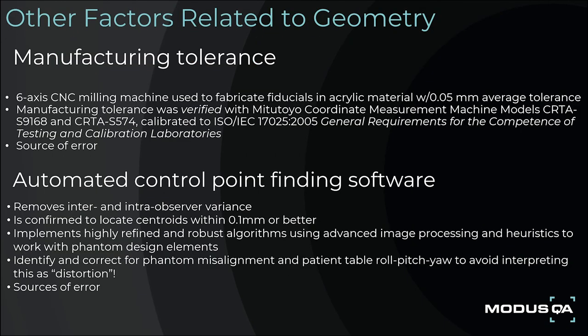Other sources of error related to geometry include manufacturing tolerances. Modus QA uses a six-axis CNC milling machine to fabricate fiducials in acrylic material with 0.05 mm average tolerance. This manufacturing tolerance was verified through the use of a coordinate measurement machine calibrated to current ISO standards. Automated software removes inter- and intra-observer variance. Our software is confirmed to locate centroids within 0.1 mm or better, implementing highly refined and robust algorithms using advanced image processing and heuristics. The software also identifies and corrects for phantom misalignment and patient table roll, pitch, and yaw to avoid interpreting these as distortion.